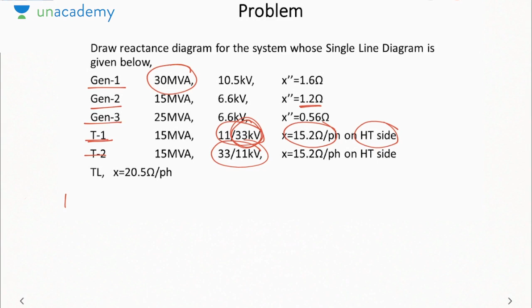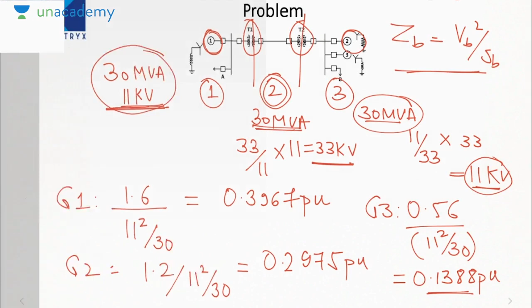Now I need to calculate the per unit impedance of the transformers and the transmission line. In the case of transformer T1, the impedance is given as 15.2 ohm on the high tension side. High tension means high voltage. Now which side is high voltage for transformer T1? The secondary side has the high voltage. So T1 is 15.2, and the base must be taken on the secondary of T1. The secondary of T1 is actually section number 2. The base is 30 MVA, 33 kV. Okay, so we have to take 33 square by 30.